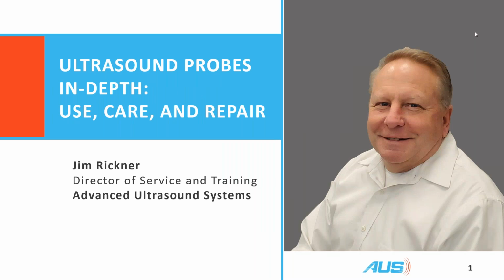Today we're going to talk about ultrasound probes. And for any of you who have worked on ultrasound, you know this is one of the high failure service items on ultrasound. This is due to various reasons. They're fragile in their very nature. Basically, crystal is a glass, so dropping them, handling them, you have to be very careful with them.